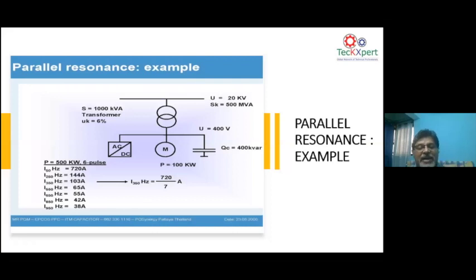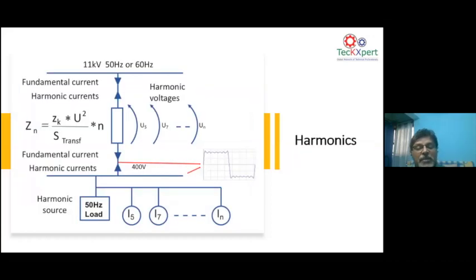That means a 100 ampere current, that is a fifth harmonic current. When it flows through the network, what happens? Fifth harmonic current will give an impedance voltage drop equivalent to the fifth harmonic impedance. See what happens in the fundamental: when you take 50 cycles, your impedance, everything is related to 50 cycles. When you take the frequency to higher and higher order, naturally the voltage drop on that impedance, the impedance also goes up proportional to the frequency.